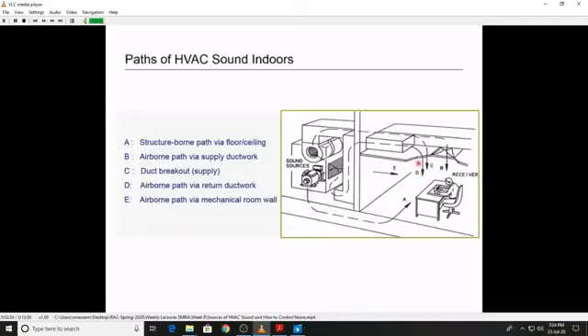And finally, the third way is breakout noise. There's sound of relatively high pressure moving through these ducts, and it can actually pass through the walls of the ducts. So even though a duct may be passing down a hallway and have no registers locally, the sound can pass through the duct walls and into a room and be perceived as noise. And finally, the structure itself will allow noise to pass through it, and that's a combination of airborne and structure-borne paths. So in HVAC, we need to worry about all of these potential paths. And so if you have a report of something being noisy, you need to be careful to try to figure out what the potential paths are that are involved.